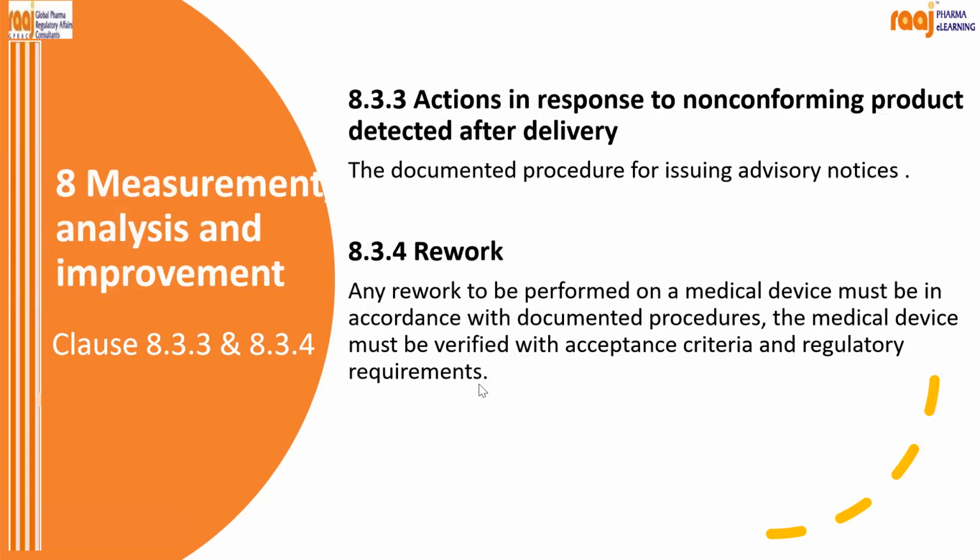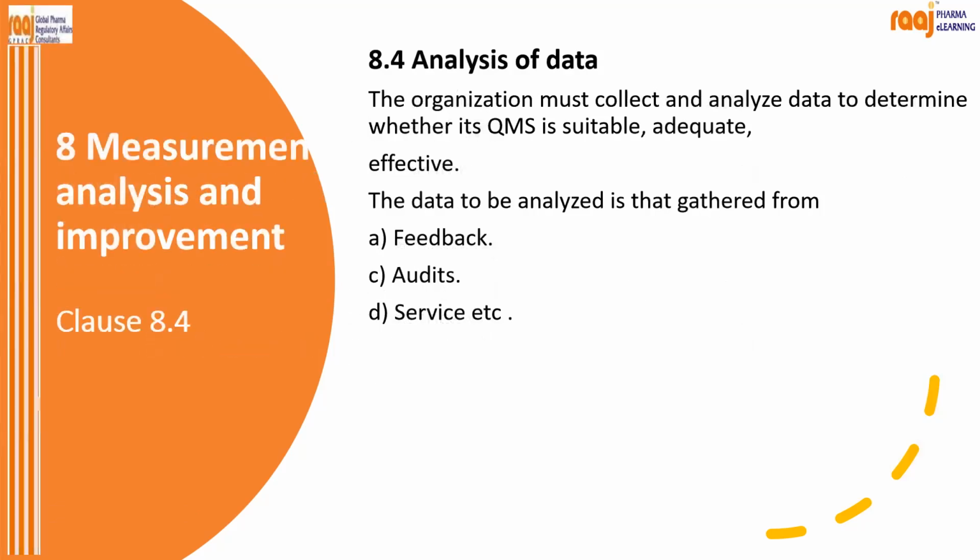Sometimes there is rework, so people use a rework policy. In your case, if it is not applicable, you can exclude this clause also, stating that rework or reprocessing is not applicable. And if it is applicable, then you have to justify it also. Any rework to be performed on the medical device must be in accordance with the documented procedure, and the medical device must be verified against acceptance criteria and regulatory requirements.